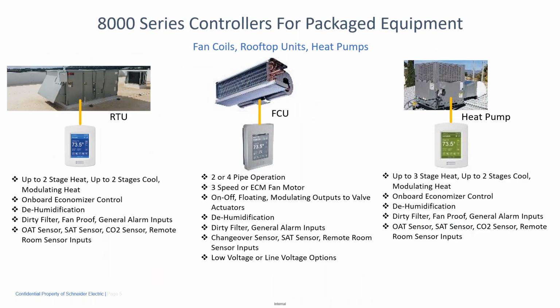The equipment that these are used on is typically packaged equipment. So we're talking fan coils, rooftop units, heat pumps, for instance. On the rooftop unit application, standard configuration is up to 2 stages of heat, 2 stages of cool, or modulating heat. You can control the economizer, so you have a 0 to 10 volt output for an outdoor damper. It can do dehumidification. Each one of these controllers does have a humidity sensor on it. You can add configurable inputs like dirty filter, fan proving, or general alarm inputs. It also accommodates adding an outdoor air sensor, supply air sensor, or a CO2 sensor if you want.